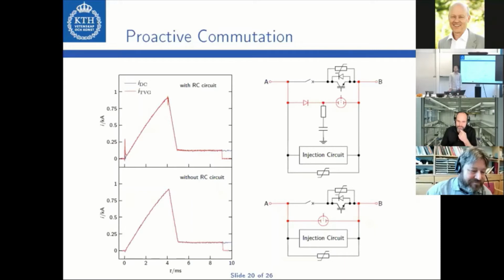So at higher voltage, or HVDC voltage, you would need to connect quite a few of them in series to operate the system in the end. Do you know if there are vacuum gaps with higher voltages available, or is that the limit of what you've shown? I think it was 50 or 60 kilovolts from the manufacturer we purchased from. So this is up to my knowledge what they offer, but I think they are also quite active in research, and when one looks at their papers, I think they have shown some switches for even higher voltage.